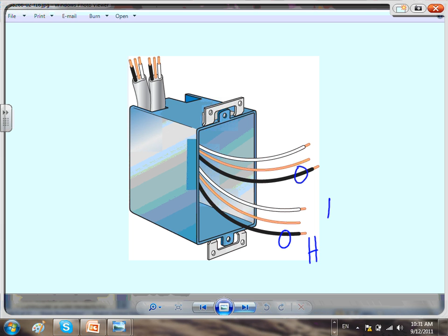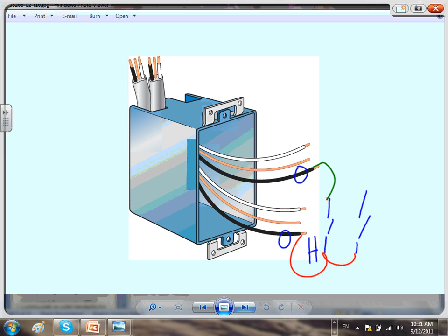If these are two switches, here's my hot 1 and hot 2. Let's say we have two switches. I bring the hot to switch number 1 and switch number 2 - how do you wire it? We bring the hot to this and this. Then this goes to my fixture number 1. I have my neutral here, capped. All my grounds are tied together, and you tie them to the side of the switches.